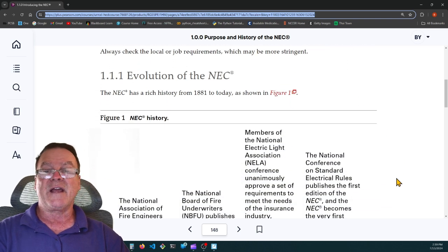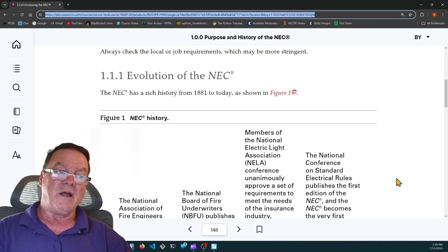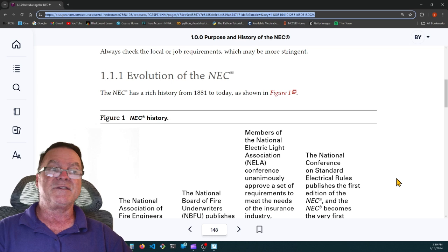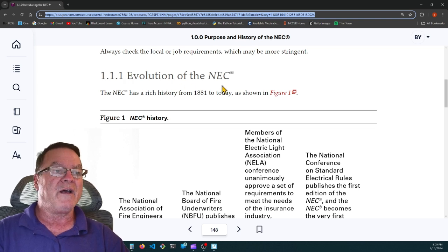One example of that is the National Electrical Code says we can use conduit as a grounding conductor. Here in Florida, most municipalities that are coastal, because of salt air, say no, you have to run an additional internal equipment ground, either insulated or bare, in the conduit, but you have to have a separate equipment ground other than the conduit because of corrosion. That conduit will rust. So that goes above and beyond the National Electrical Code.